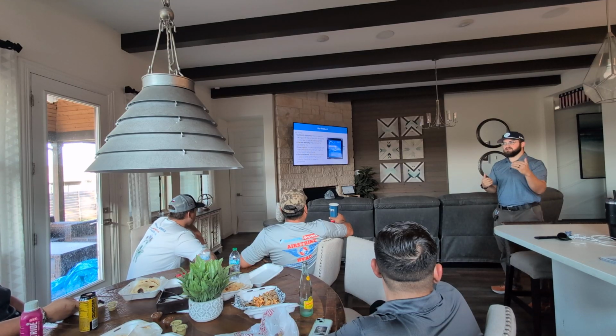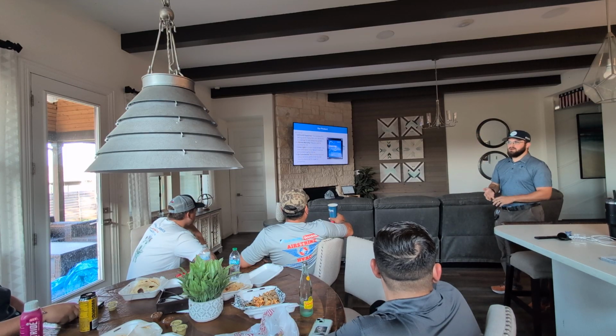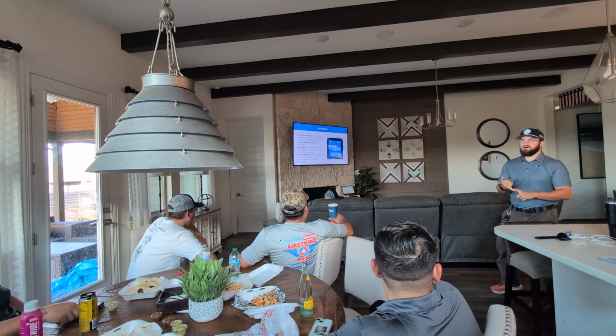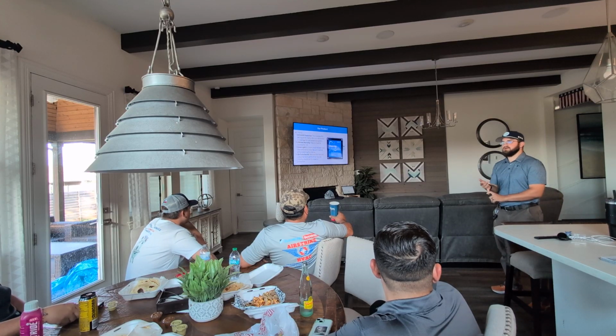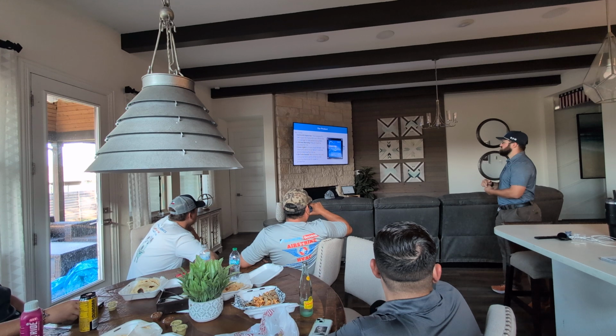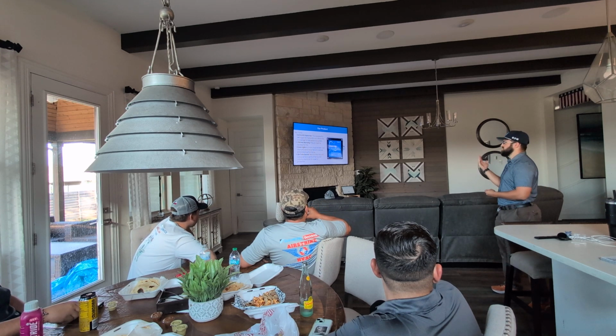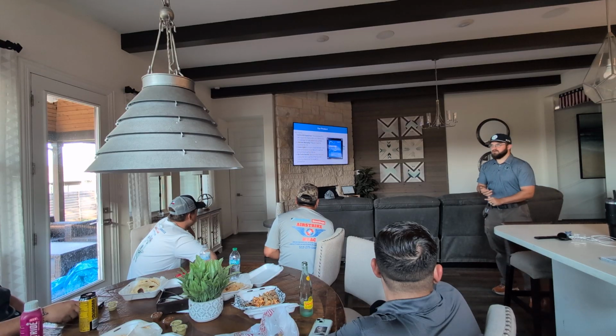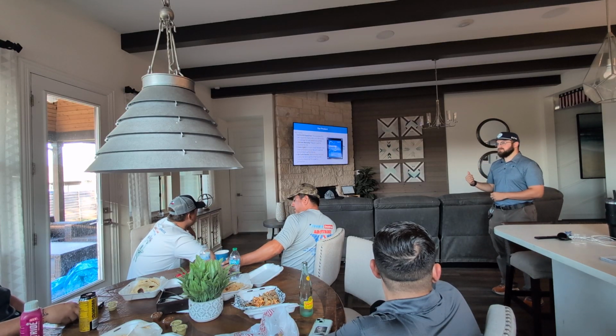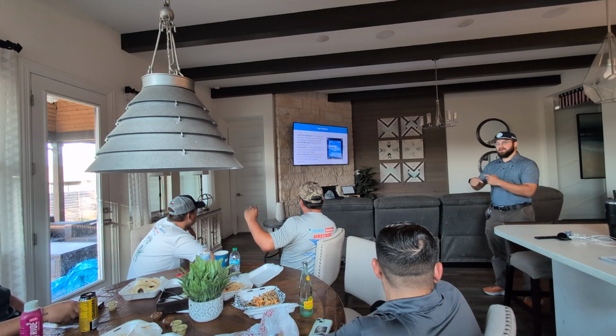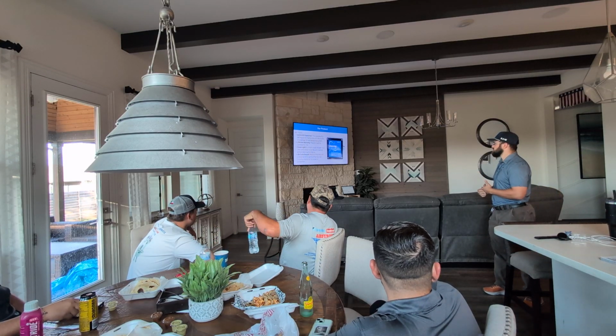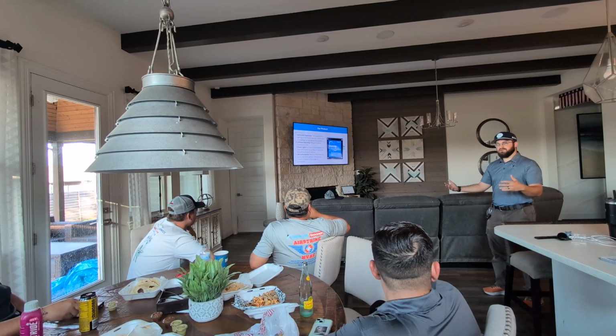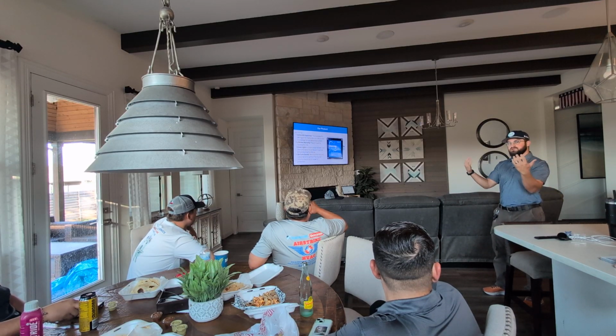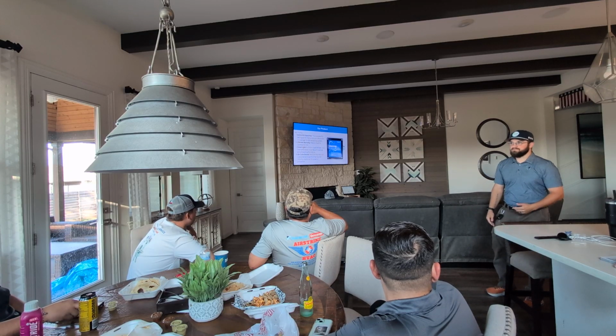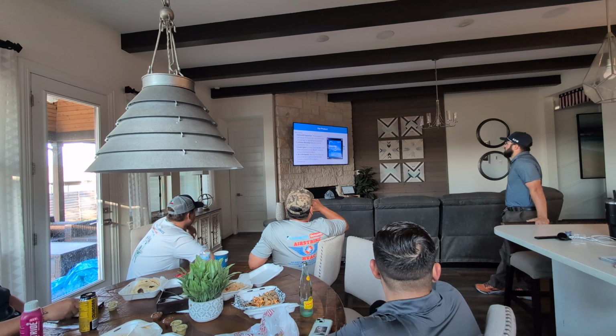Several competitors do less. This one is 120 kVA, basically the same as your entire panel's worth of breakers. Competitors do 108 and 102, like the Eaton Ultra and the Siemens, and they do worse at it. So this one exceeds them in every possible way. The short circuit current rating, the SCCR, is 200 kiloamps, which is the important part - how quickly it can take a surge and how much of a surge it can take. That's the same as a 400 amp system, which we don't deal with a lot. When we do deal with a 400 amp system, they usually have 2 separate panels, and we'll put one on each panel at the main panel, so they essentially have the 400 amps covered.